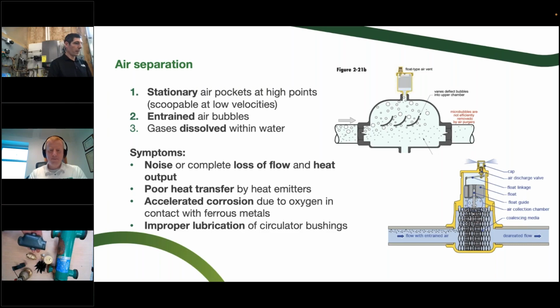So this is commonly called a camel hump in the industry just because of the shape of it. I call it a coupling because that's really all it's doing, it's coupling the pipe. And the technology inside one of these is, number one, it's a big space. Whenever water comes into a space like this, that's called a low velocity zone. So the water slows down as it comes through here for the brief period of time that it goes through there. Notice there's a little ramp to encourage the air to go up to that little vent that would screw into the top there. And you can see the little tab that sticks down there trying to grab some of those little micro bubbles as they come through. But really you're dependent on the velocity slowing down. There's really no media.